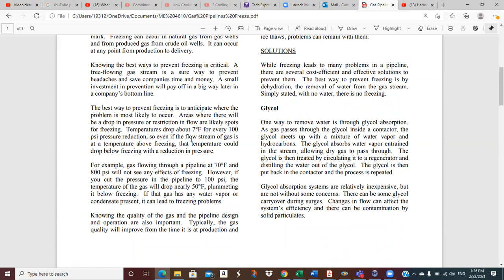So even if the flow stream of gas is at a temperature above freezing, that temperature could drop below freezing with a reduction in pressure. And so, well, you know, it's colder than bejeebers. So everybody that's using natural gas is pulling max natural gas out of the pipeline. What happens to the pipeline pressure? It falls. I mean, you know, it's pretty simple.